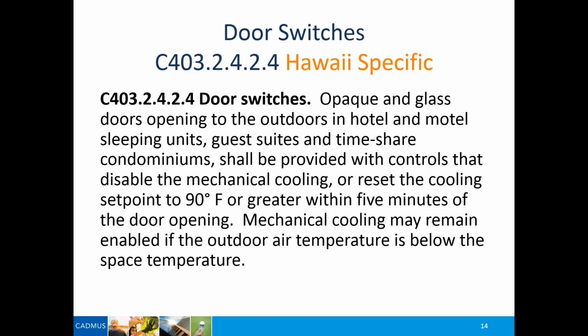So we have this Hawaii-specific provision that says that if a lanai door is open for more than 5 minutes, the air handler in the room shuts off and goes to a default of 90 degrees F. Makes all kinds of sense, as studies have shown that the per room energy savings is pretty darned tremendous. And we expanded this not just to hotels, but to timeshare units, because we're all aware that some hotels are converting to timeshare, much to the discomfiture of the unions. And we've extended that to condominiums and guest suites as well. So a very simple measure, very Hawaii specific, and very, very effective in terms of saving energy.